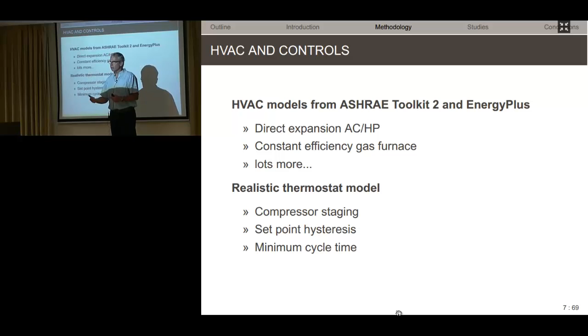The refrigeration system has a compressor turning on and off, and we have a thermostat with a set point and hysteresis. Also, in the model, we have to consider what we call minimum cycle time. When you turn a compressor on and then off again, you cannot turn it back on right away; you have to wait a little bit for the refrigerant to settle. That's minimum cycle time.